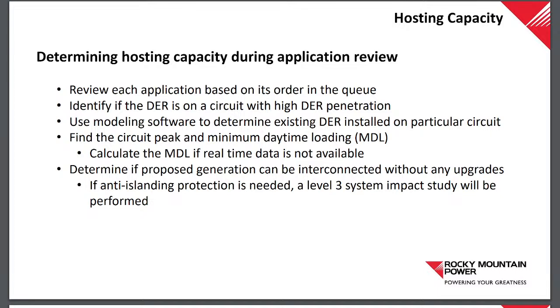That's when our generation is creeping up to, at, or exceeding our minimum load. We don't want any reverse flow at our circuit breakers or line reclosers. So we use modeling software to determine the existing generation installed on that circuit, and the big thing is coming up with a minimum daytime load amount. We take the hours of 8 and 9 a.m. to 6 p.m. to determine what we see as the minimum load.